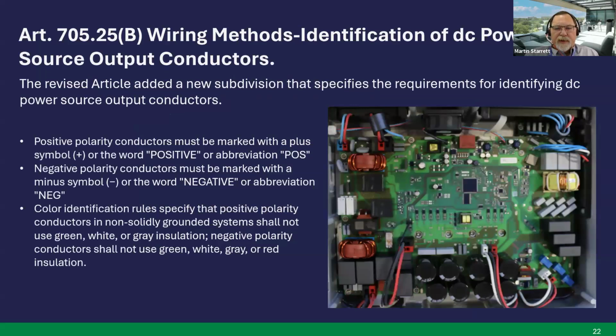705.25B, wiring methods, identification of DC power source output conductors. The revised article added a subdivision that specifies the requirement for identifying DC power source output conductors. Positive polarity conductors must be marked with a plus symbol or the word positive or abbreviation POS. Negative must be marked with a minus symbol or the word negative or abbreviation NEG.